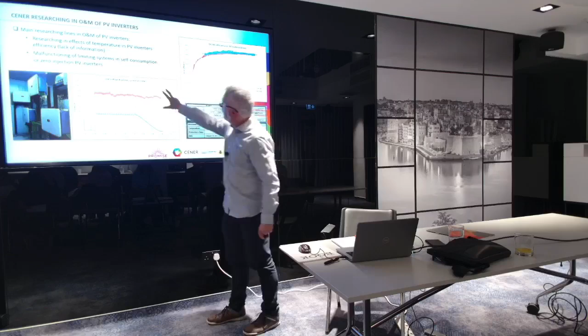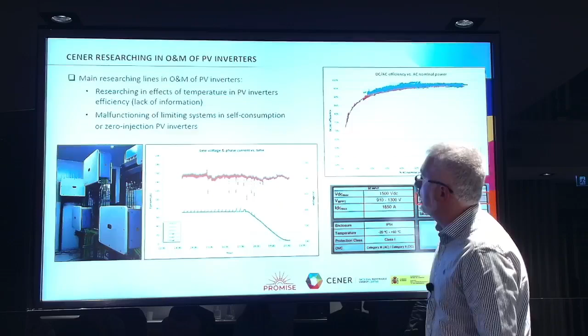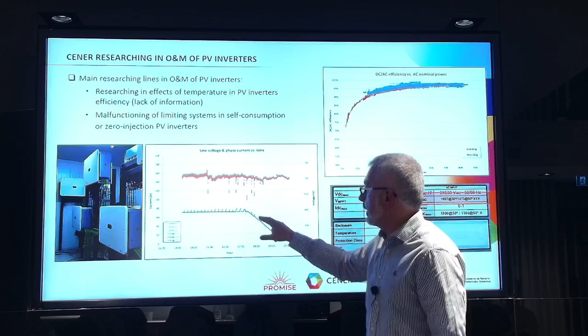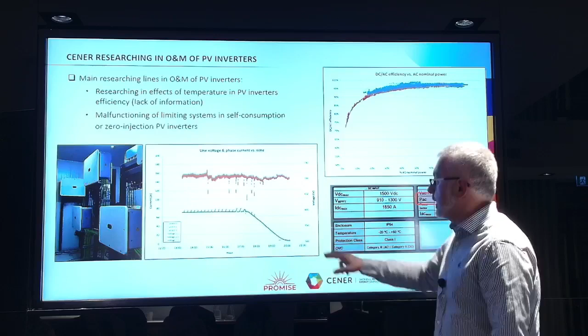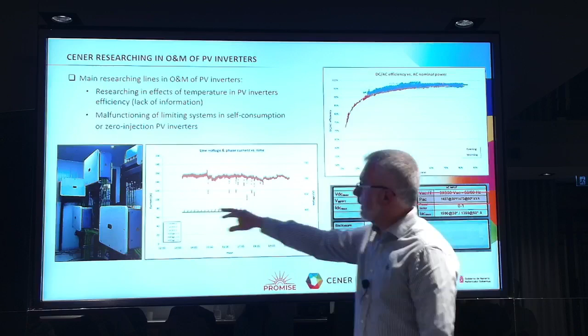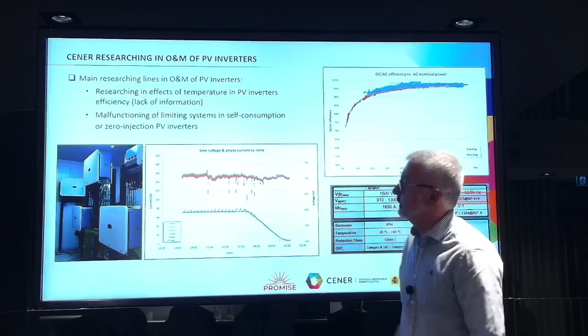In this graphic, we can see some other events like limitations of the injected current regarding unknown events. This inverter should inject following the curve of the radiation, but in this case it's limited. This is a malfunction of the PV inverter.